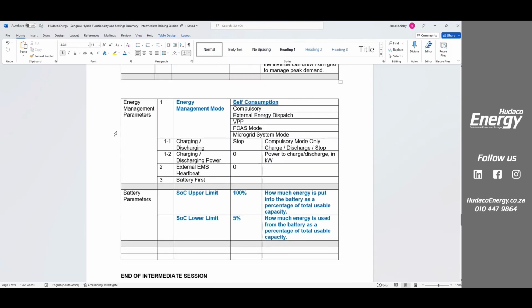The next one is our energy management, and this here is where we choose our operating mode. So I spoke to you that there are multiple modes available. For South Africa, we use self-consumption, we use compulsory, or we use microgrid system. So only those three we would use. Once you select self-consumption, it'll bring up a new menu that says charging, discharging, and how much power you want to do that with. So this is where you would do that under energy management parameters.